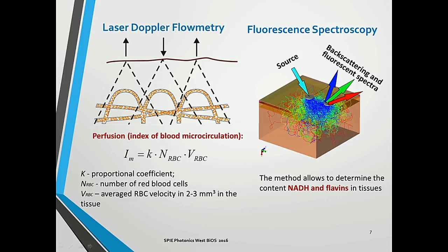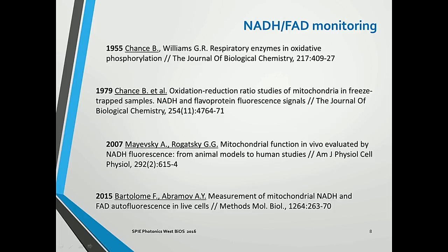And what we actually offer is a pretty simple method. It's laser Doppler flowmetry to measure blood flow, which we call blood perfusion, calculated quite simply from the number of red blood cells per volume for the wavelength we use, 1064 nm. And fluorescence spectroscopy addresses the question of the level of metabolic activity in the tissue, which really affects whether the patient has a problem with vessels in the foot. It then brings a second effect, developing necrosis in the skin and tissue.